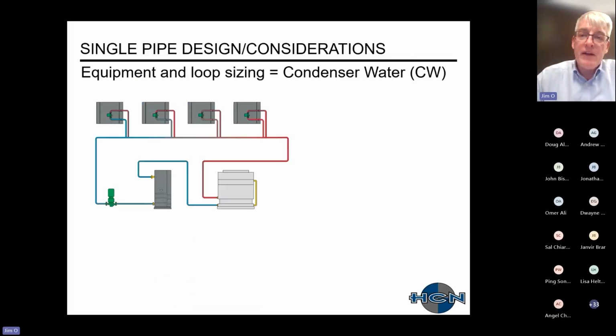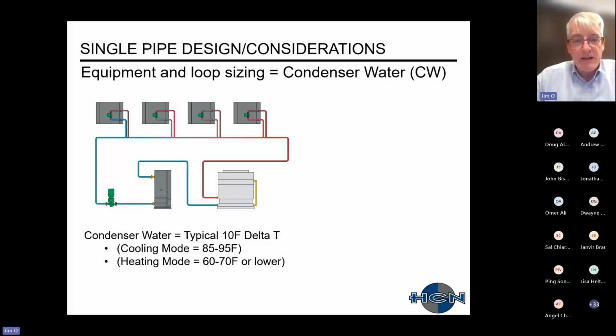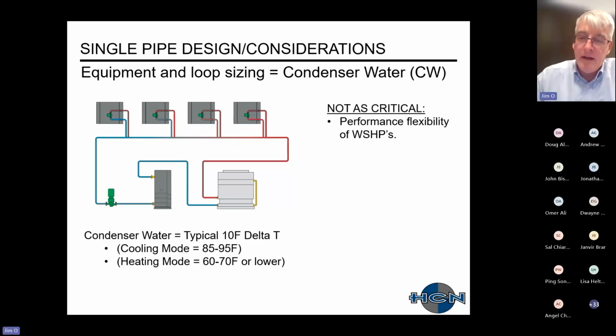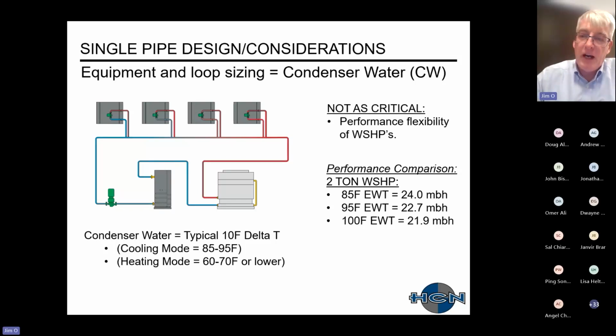Condenser water loops, once again, are pretty flexible. The typical condenser water loop that I've seen has a delta T of 10 degrees, for cooling as well as heating. And once again, because of the water source heat pumps, their performance is not really affected that much by different temperatures. So say in this example, just to exaggerate, the unit on the far left would receive 85-degree water. It would be able to produce 24 MBH, or approximately 2 tons.